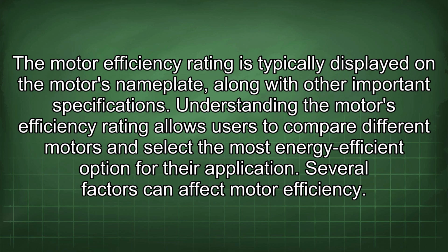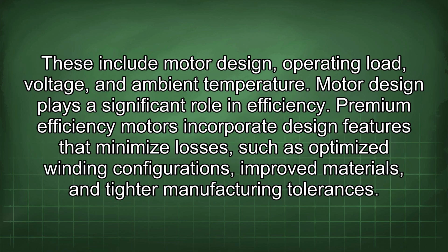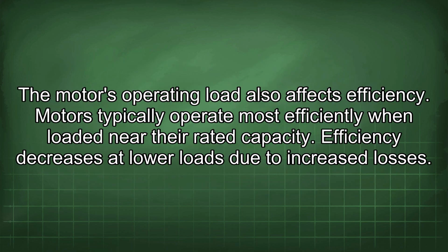Several factors can affect motor efficiency. These include motor design, operating load, voltage, and ambient temperature. Motor design plays a significant role in efficiency. Premium efficiency motors incorporate design features that minimize losses, such as optimized winding configurations, improved materials, and tighter manufacturing tolerances. The motor's operating load also affects efficiency. Motors typically operate most efficiently when loaded near their rated capacity. Efficiency decreases at lower loads due to increased losses.